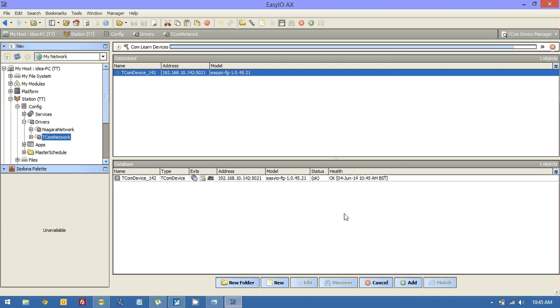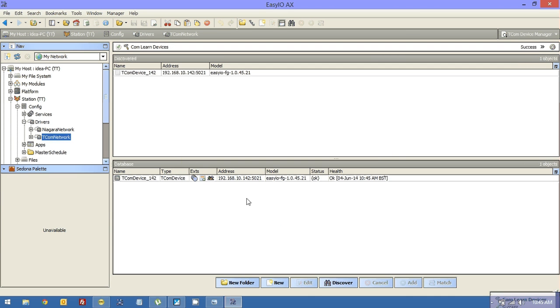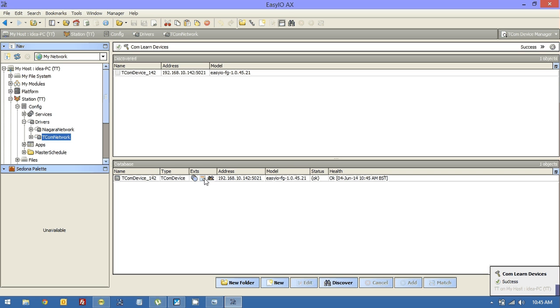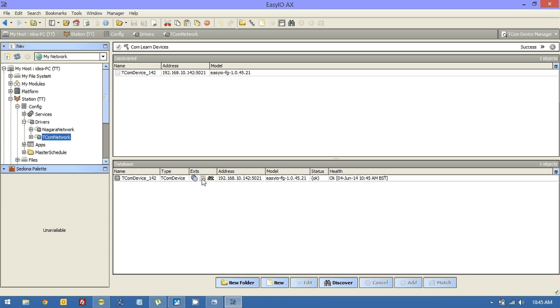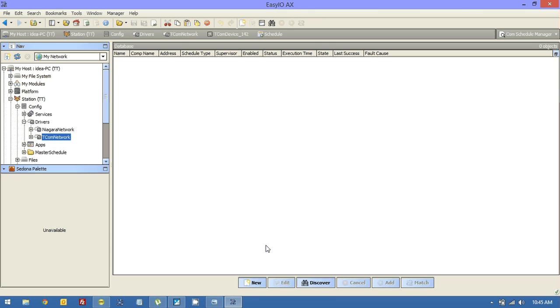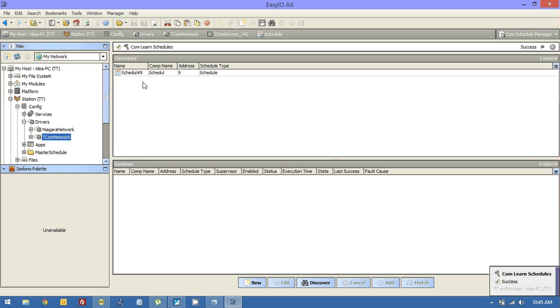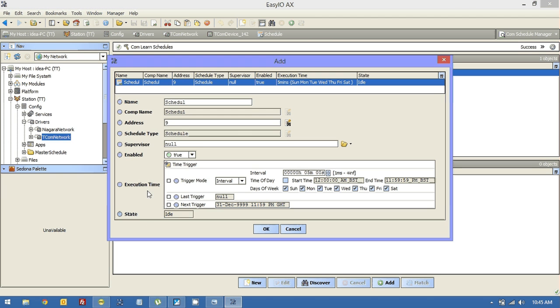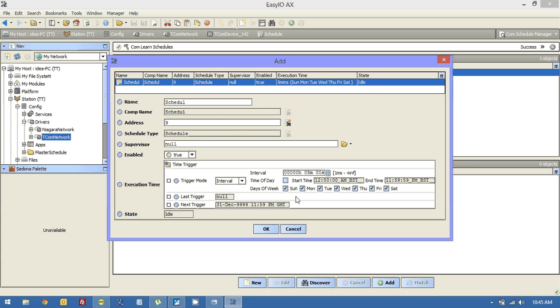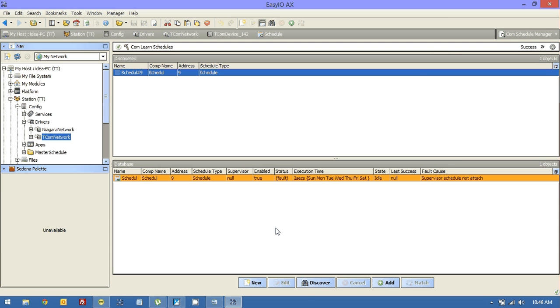When that's finished, what I can do is bring that in as a device. And what you will see now, you'll see the health is okay. Now you're going to see points, schedules, and histories. If I start with schedules and do a discover, it's going to bring in that schedule that we just created. That currently has nothing in it. But I'm going to set it to update automatically to two seconds. And there you go. It's keeping it nice and simple. Supervisor schedule doesn't match, which is correct. It doesn't because I've not allocated it yet. That's why it says Supervisor Null.